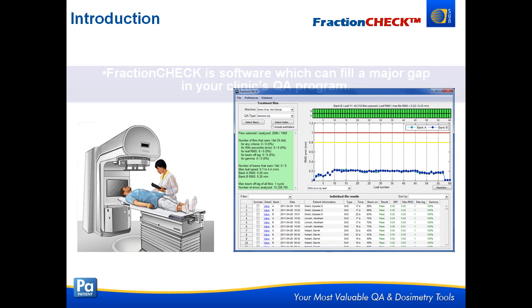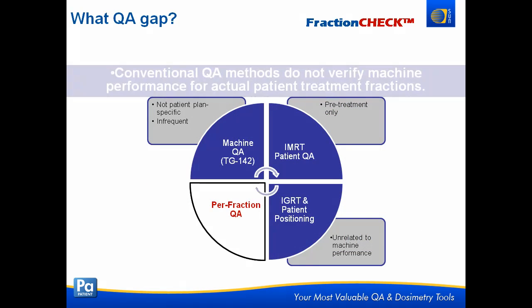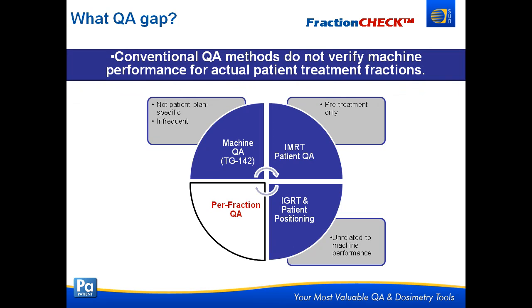Next I'd like to talk about FractionCheck. FractionCheck is a newer tool that fills a major gap in a lot of people's QA programs. Right now, all of our conventional QA methods aren't verifying machine performance for actual treatments. We do a lot of machine QA, but that's not patient specific and it's every week or every month. We do per-patient IMRT QA, but that's usually just pre-treatment. We assume the rest of the fractions are going well. Every day the patient comes in we do IGRT and patient positioning, but it's unrelated to machine performance. This gap of per-fraction machine performance is where FractionCheck comes in.